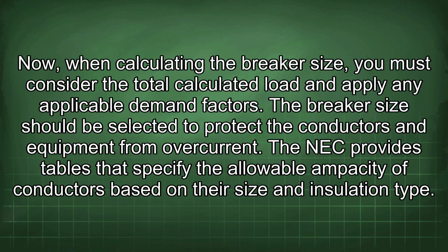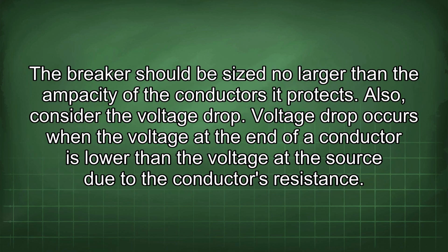Now, when calculating the breaker size, you must consider the total calculated load and apply any applicable demand factors. The breaker size should be selected to protect the conductors and equipment from overcurrent. The NEC provides tables that specify the allowable ampacity of conductors based on their size and insulation type. The breaker should be sized no larger than the ampacity of the conductors it protects.